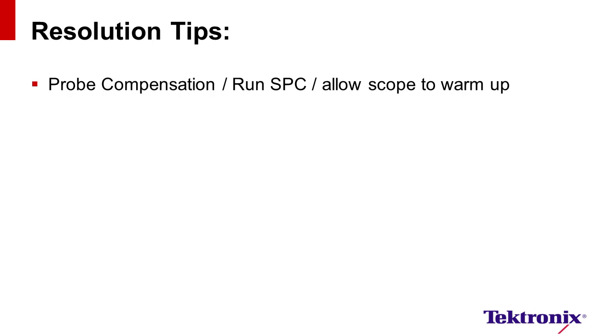Let's begin with a few simple best practice techniques for maximizing resolution and scope performance. The first one is preparing the scope. Make sure it's warmed up, had a recent self-calibration, and probe compensation has been performed.